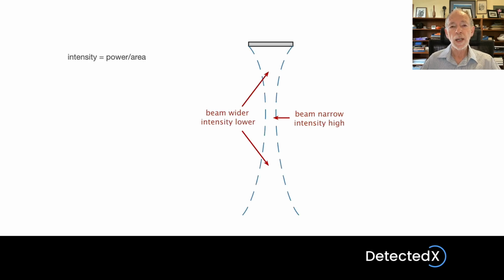Now I want to introduce a couple of concepts that help you to understand how ultrasound machines actually focus the ultrasound beam. This one relates to the way intensity varies at different depths within the ultrasound beam. So let's first define what we mean by that beam. We mean the pathway that the ultrasound travels within. So when I talk about the transmit beam, I mean that defines the pathway that the transmitted ultrasound energy travels along. So the transmitted ultrasound is basically constrained to be within this beam, and therefore the beam defines exactly where the ultrasound will be interacting with the tissues.